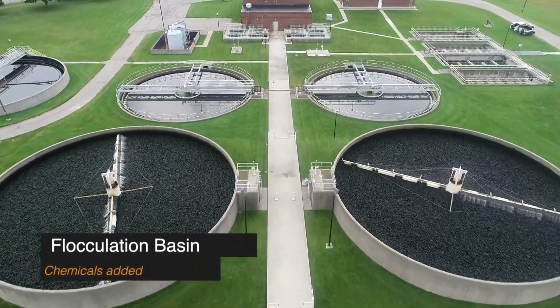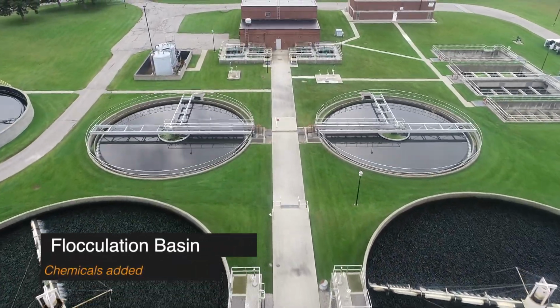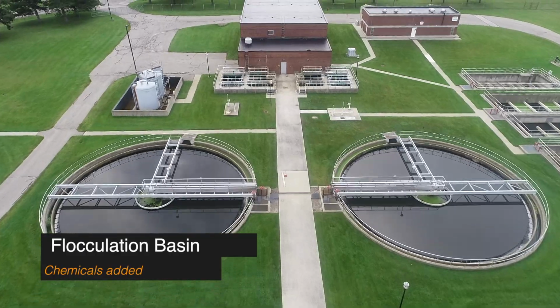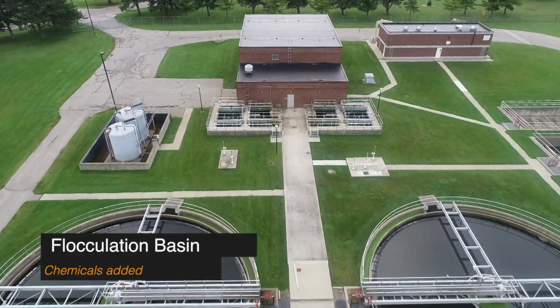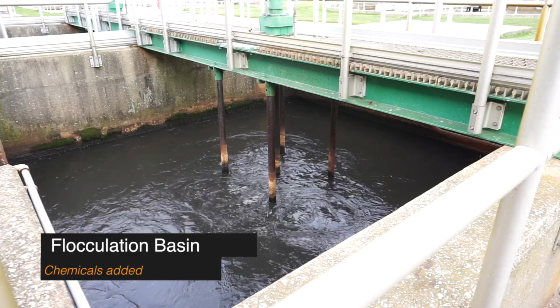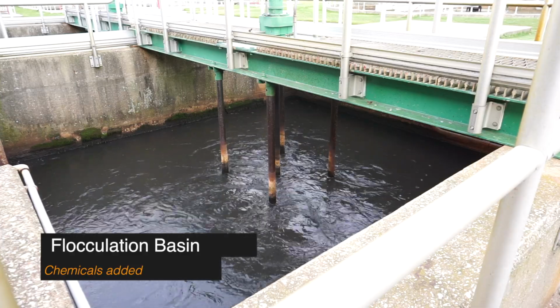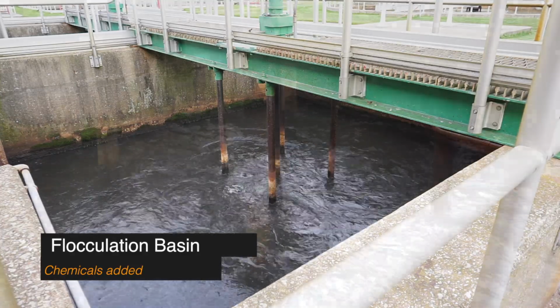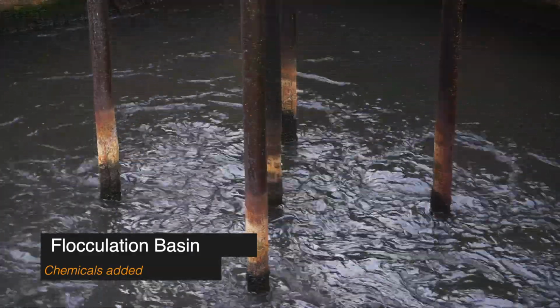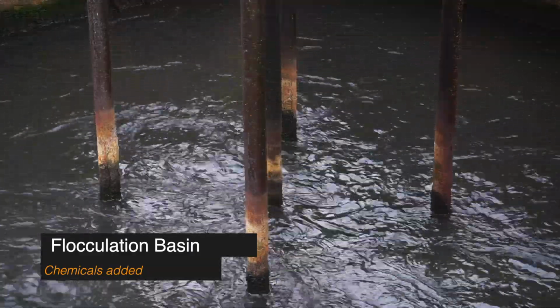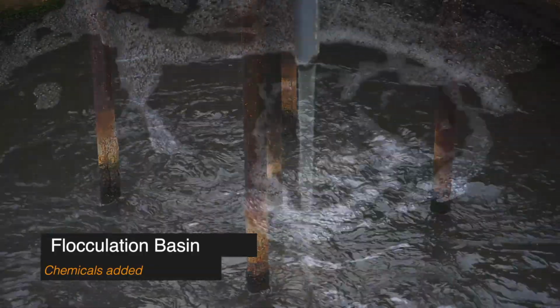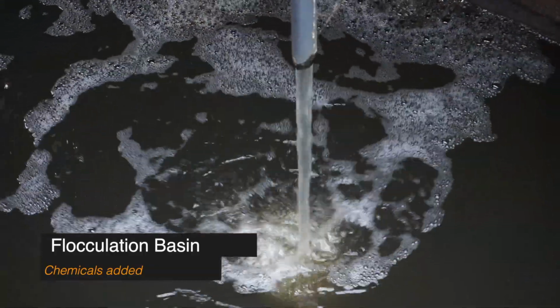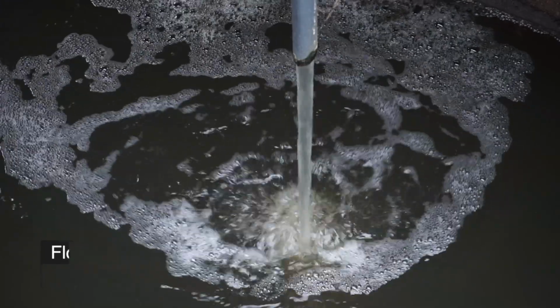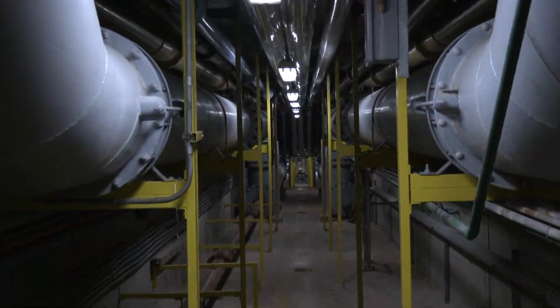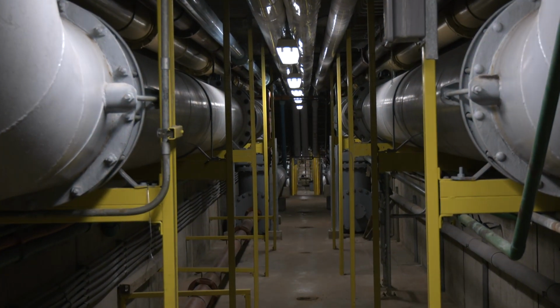Here we add chemicals to further remove any phosphorus that the biology wasn't able to utilize. First, ferric chloride is added to bond with the remaining phosphorus. The mixing action in the tank causes the particles to flocculate to create larger particles. Then a polymer, polyacrylamide, is added to coagulate the particles into even larger particles. This aids in settling out the remaining suspended solids, which is rich in phosphorus, in the final clarifier. The settled sludge is returned to the primary settling tanks where it is removed to the digester system.